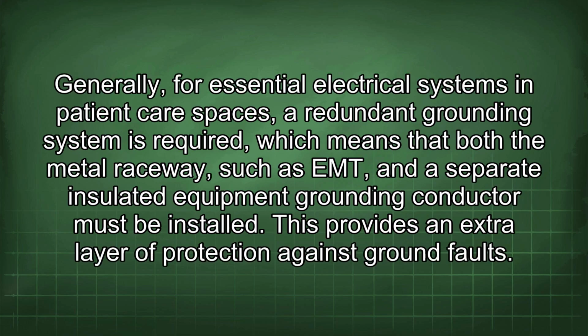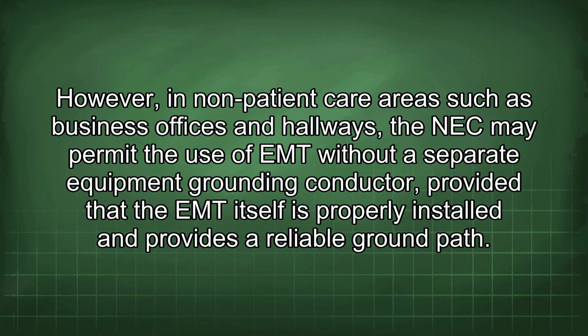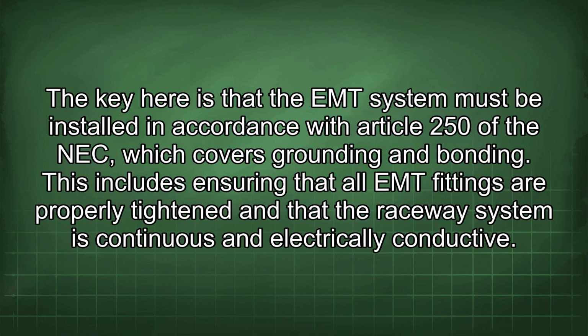Generally, for essential electrical systems in patient care spaces, a redundant grounding system is required, which means that both a metal raceway, such as EMT, and a separate insulated equipment grounding conductor must be installed. This provides an extra layer of protection against ground faults. However, in non-patient care areas such as business offices and hallways, the NEC may permit the use of EMT without a separate equipment grounding conductor, provided that the EMT itself is properly installed and provides a reliable ground path. The key here is that the EMT system must be installed in accordance with Article 250 of the NEC, which covers grounding and bonding. This includes ensuring that all EMT fittings are properly tightened and that the raceway system is continuous and electrically conductive.